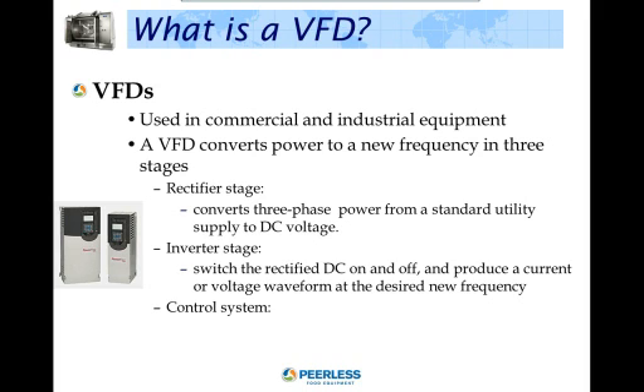A VFD converts 50 or 60 hertz power to a new frequency in two stages, the rectifier stage and the inverter stage. This conversion process incorporates three functions. The rectifier stage: a full wave, solid state rectifier converts three-phase 50-60 hertz power from a standard utility supply to either a fixed or adjustable DC voltage. The inverter stage: electronic switches or power transistors switch the rectified DC on and off and produce a current or voltage waveform at the desired new frequency. Then we have the control system. This electronic circuit receives feedback information from the driven motor and adjusts the output voltage and frequency to the selected values. Usually the output voltage is regulated to produce a constant ratio of voltage to frequency, or volts per hertz. Controllers may incorporate many complex control functions.